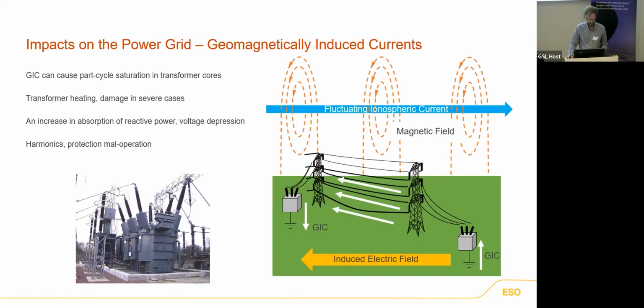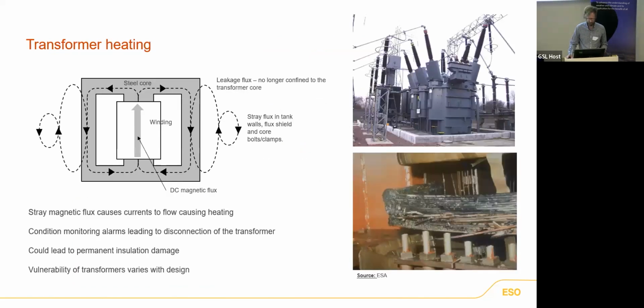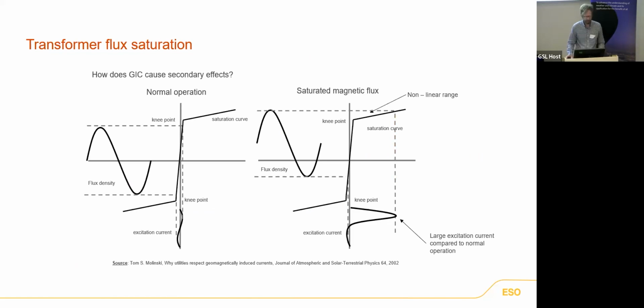So let's start with the transformer flux saturation. This curve explains how the GIC causes the excitation current in our transformers to increase. On the left, we've got a graph with the magnetic flux within the transformer on the y-axis and the current on the x-axis, with the flux density shown by the sine wave, and how that transfers into the excitation current. Excitation current is just a small part of the current within a transformer—it's the current required to set up the magnetic field within the transformer.